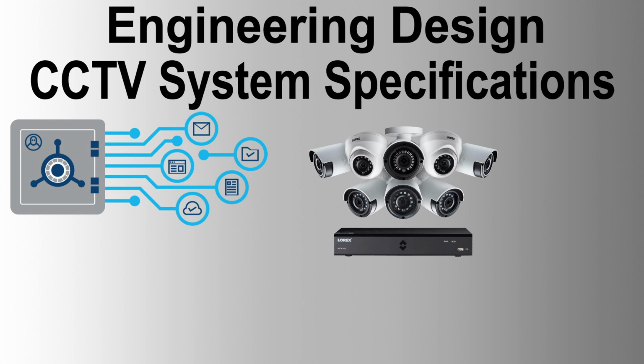Camera types. Fixed type cameras, used for intrusion detection using video motion detection, VMD, techniques. These cameras are located at fence areas covering the complete perimeter of the facility. Pan, tilt, and zoom, PTZ type cameras, used for monitoring process areas and access gates, both entry and exit gates, for surveillance purposes. The pan, tilt mount, and zoom shall be controlled from remote areas using fiber optic cables.